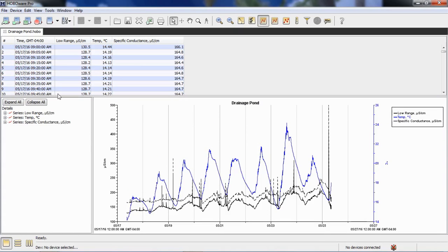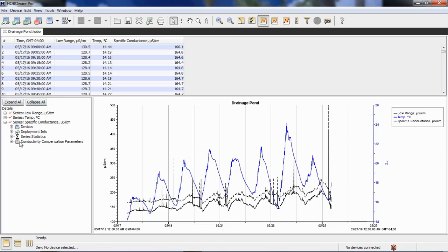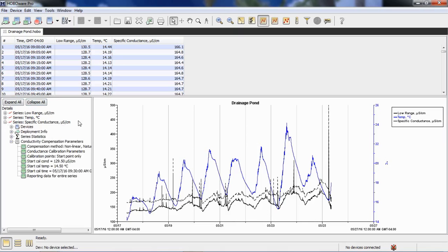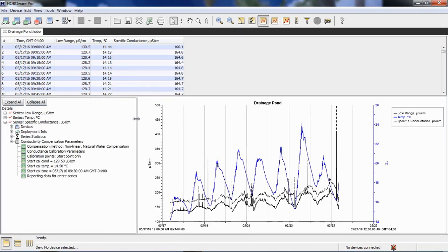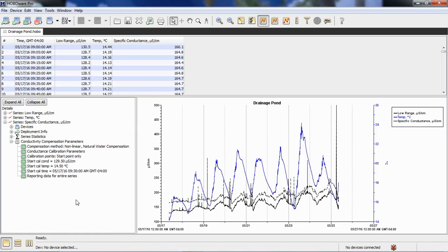So we have it in our data table. If we click on in what we call the details pane and click on the specific conductance channel, there's a selection that says conductivity compensation parameters. We can click on that and it gives us all the information about the values that we used for that starting field calibration. We're calibrating the data. We're not calibrating the logger itself.